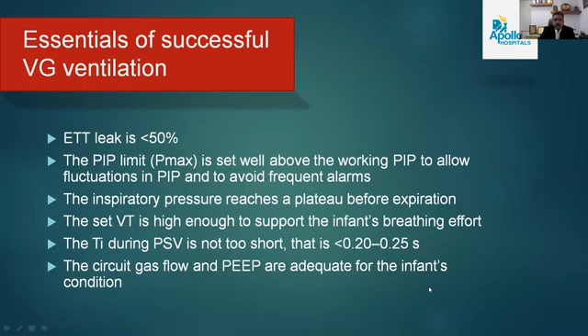So in the ET tube, there is a gas leak around the uncuffed neonatal ETT, and it varies with diameter, airway pressure, and duration of ventilation. We have seen many times, if you are ventilating for a little longer, generally after 2 or 3 days, the ET tube which was fitting snugly starts showing a leak of around 30% or 40%. That indicates you should not continue as it is, but re-intubate and put a bigger size ET tube.